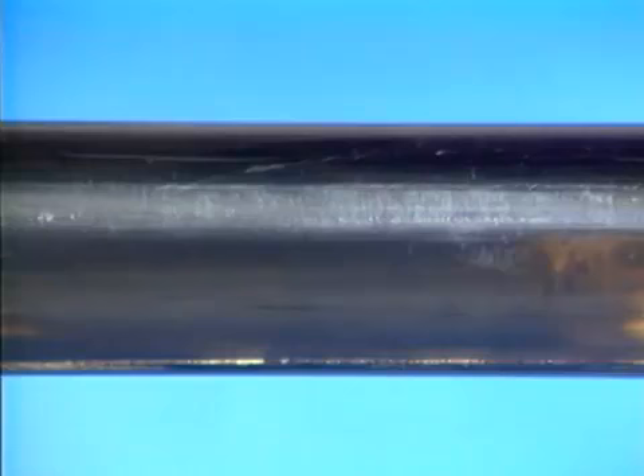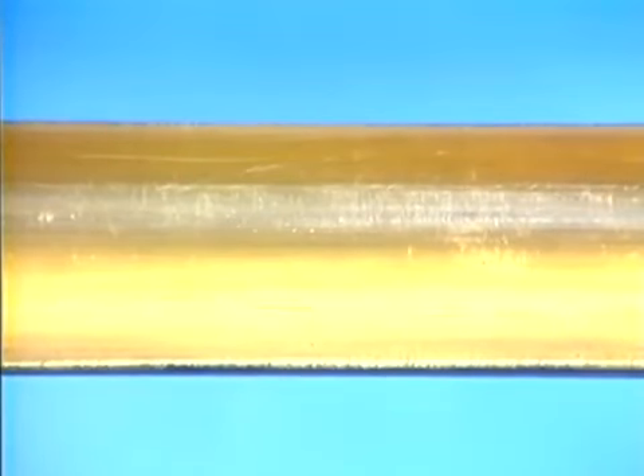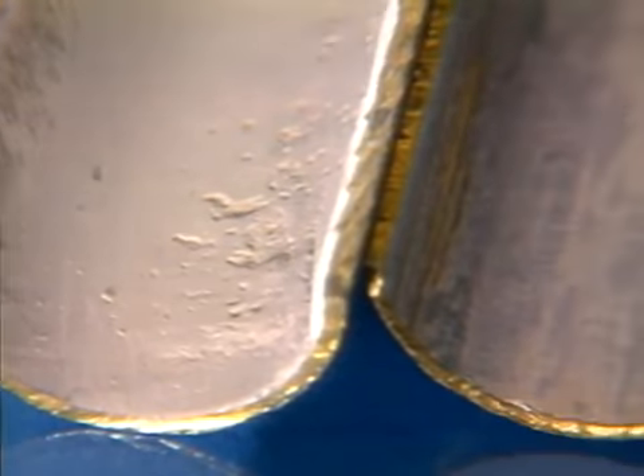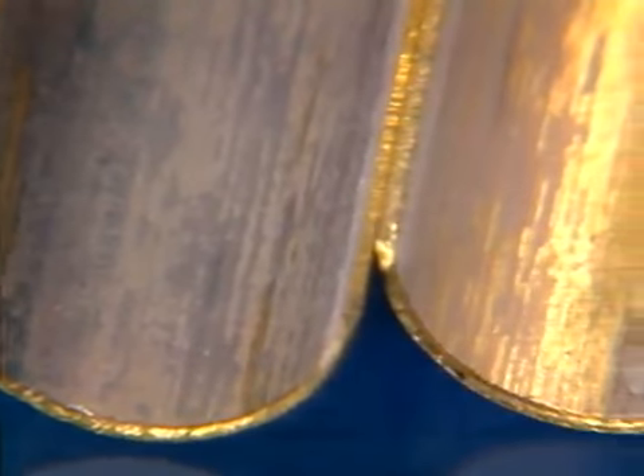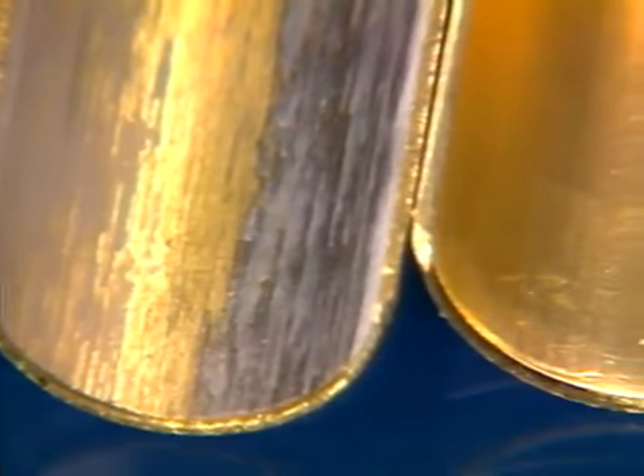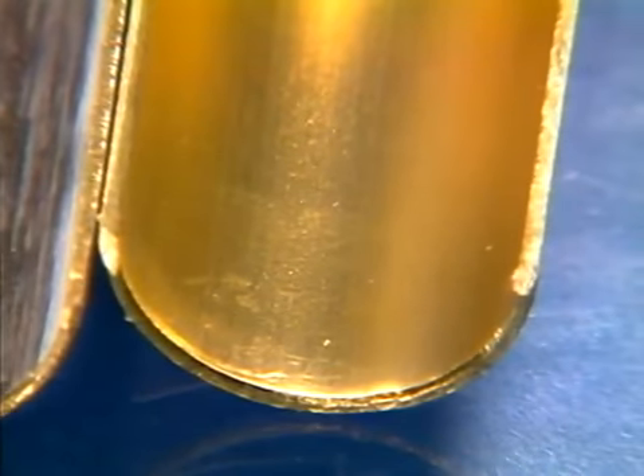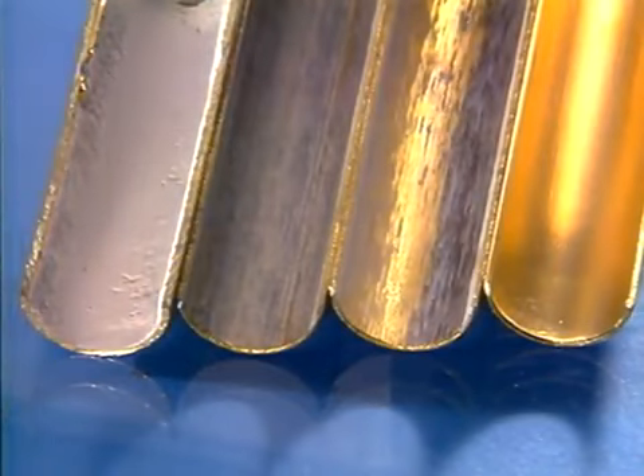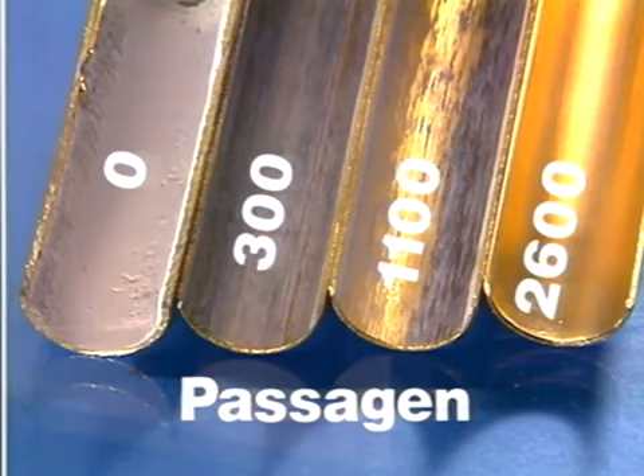The ball removes soft deposits in a single passage. Harder sediment needs an additional scraping, a job for coated cleaning balls. To remove scaling and restore the heat exchanger to its original efficiency, coated balls may need to be circulated several thousand times. But this takes only a few days. Subsequently, cleaning is continued with uncoated balls to stabilize the heat exchanger at its rated level.